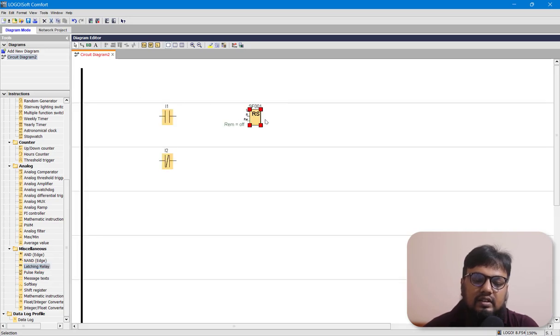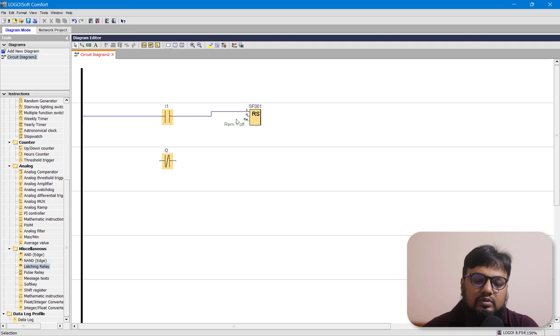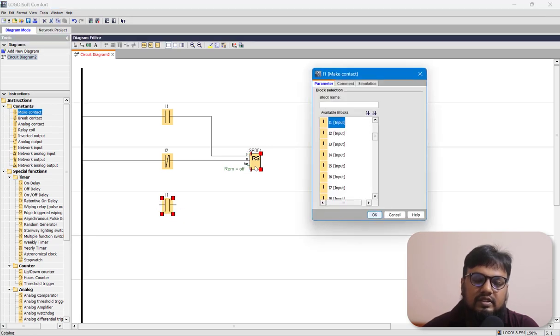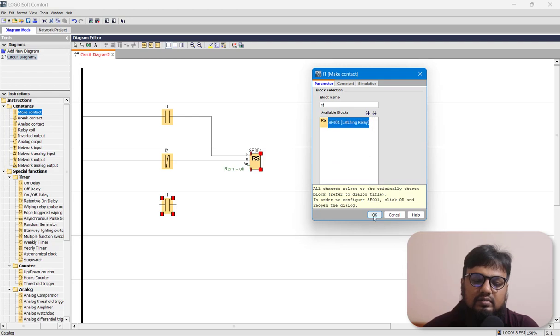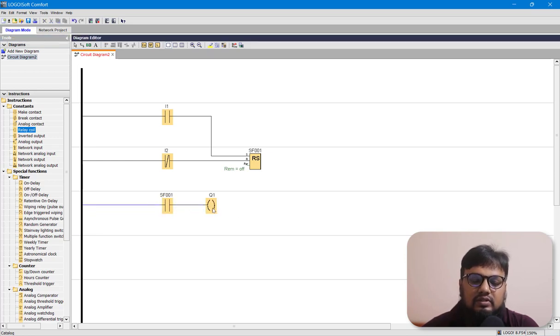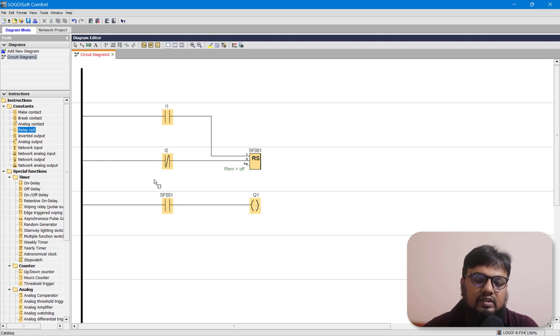This latching relay will have the contacts for our water tank. I am connecting I1 to set and I2 to reset. Now let's bring in another make contact — this is basically for SF001 — and connect that to our fill valve output coil. Whenever I press I1 (the start switch) it will set the latching relay, the open contact will be closed, and our fill valve will activate.